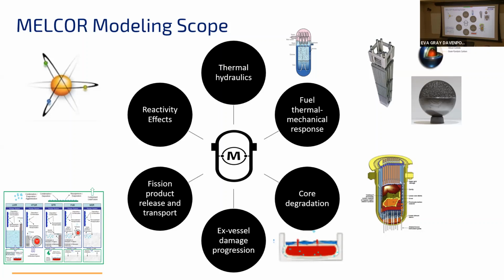For a lot of those design restrictions and everything, we've always kind of focused that our fuel is going to be solid and stationary. Do we have the ability to open that up to a salt reactor where the fuel is now moving? So for our reactivity effects, we actually have developed and implemented a point kinetics model for flowing fuel. Yeah, so that's actually in there. We actually just put that in there this last year. I didn't want to go into these details, but we actually did benchmark it quite well against the MSRE. There's a zero power pump coast down test, and it actually captured the key phenomena quite well.